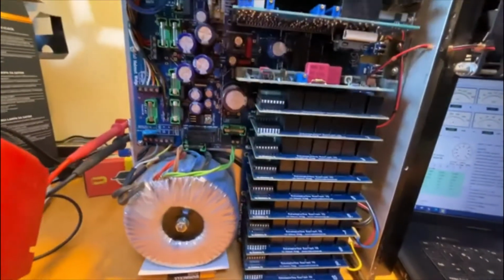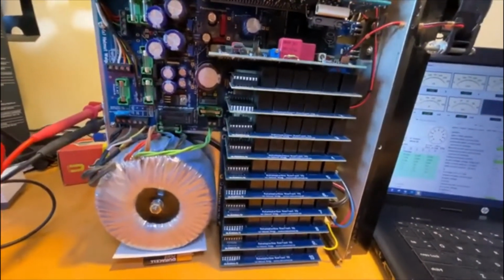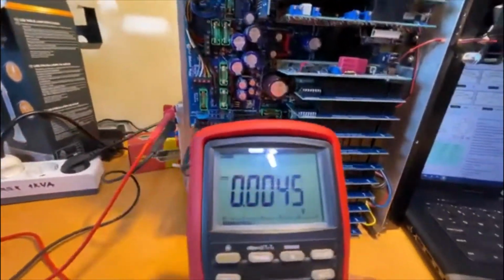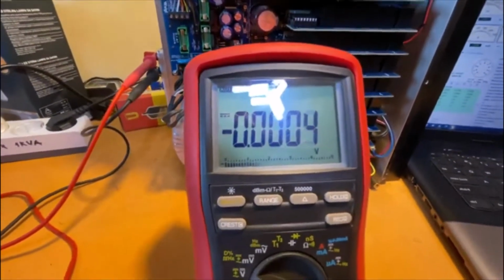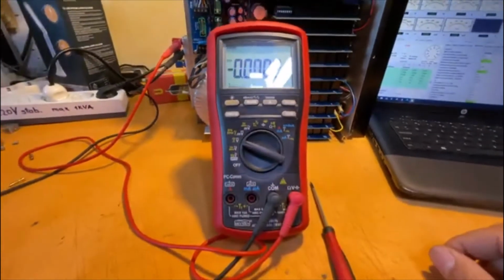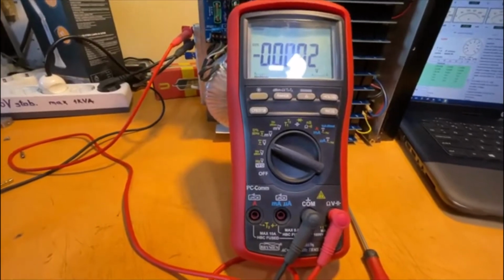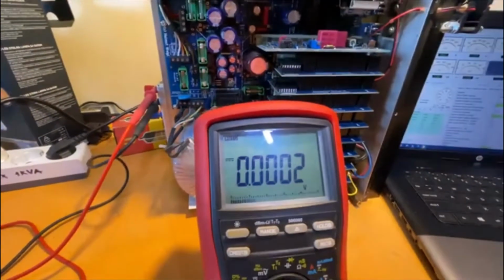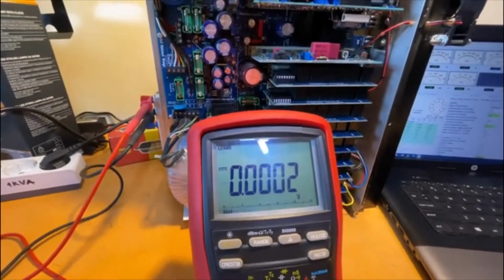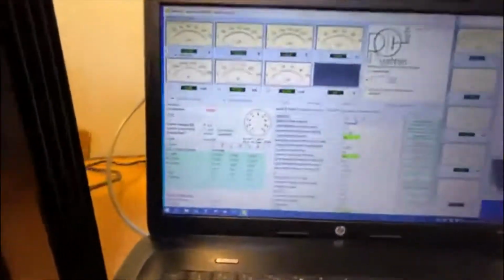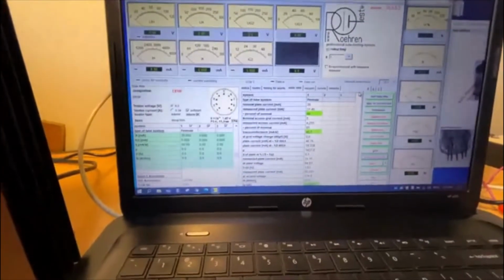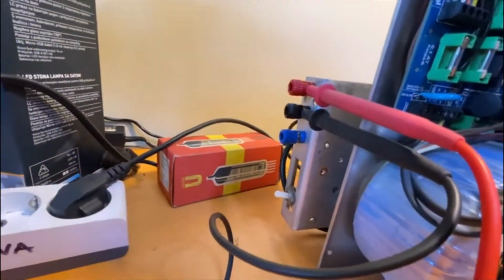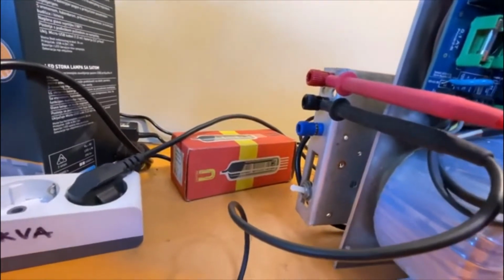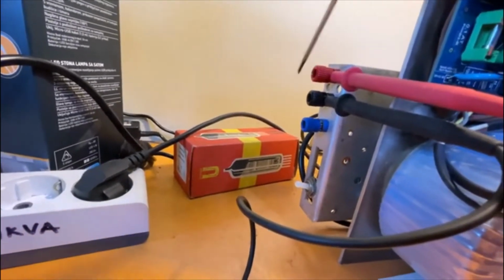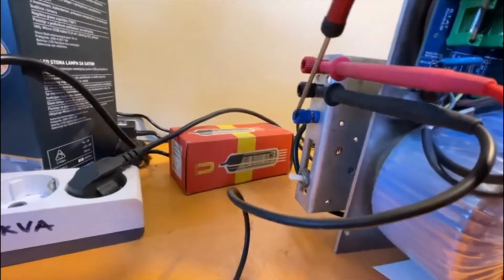For calibration, we need the calibration box, which I showed you before, a good voltmeter and ampere meter. This is a BM869, a very good one, with very high accuracy. And the software will help us very much. The multimeter is connected to the calibration box at the voltage socket. We have voltage, common, ground, and current.